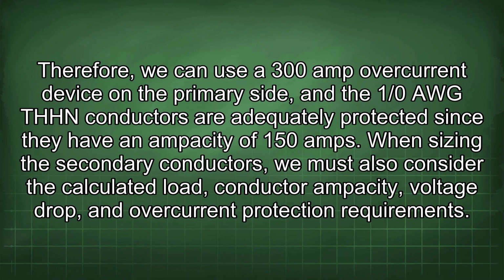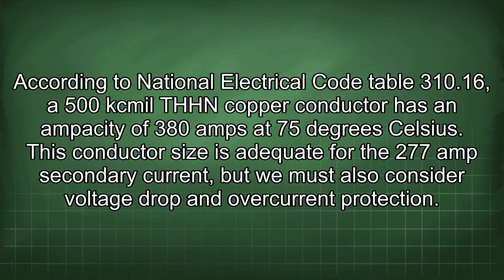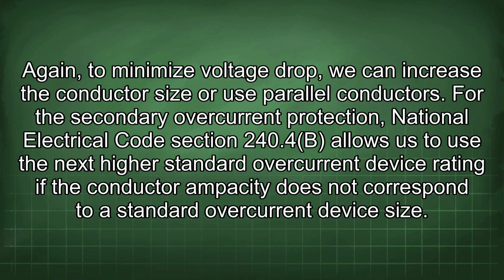When sizing the secondary conductors, we must also consider the calculated load, conductor ampacity, voltage drop, and overcurrent protection requirements. According to National Electrical Code Table 310.16, a 500 kcmil THHN copper conductor has an ampacity of 380 amps at 75 degrees Celsius. This conductor size is adequate for the 277 amp secondary current, but we must also consider voltage drop and overcurrent protection. Again, to minimize voltage drop, we can increase the conductor size or use parallel conductors.